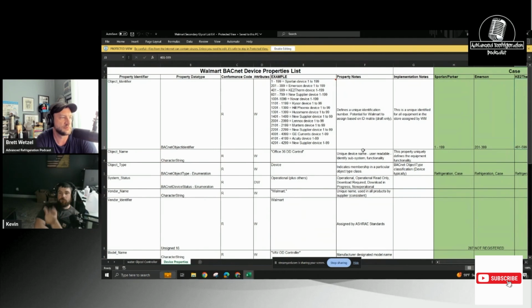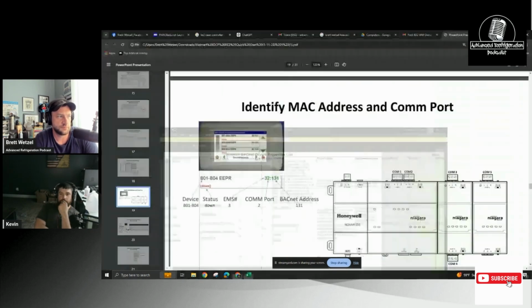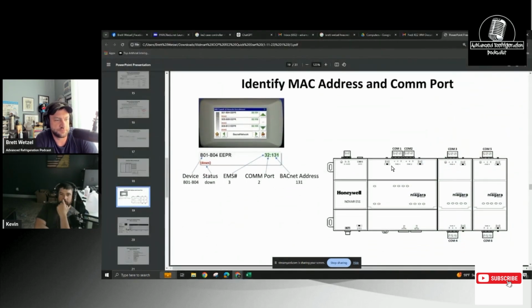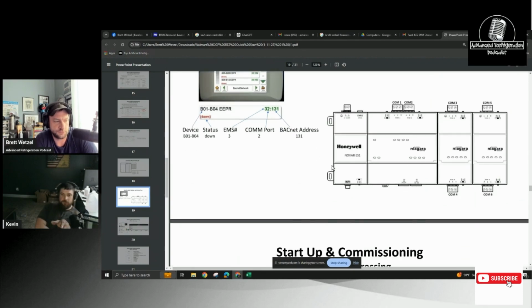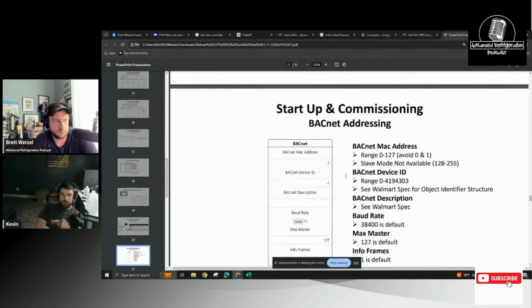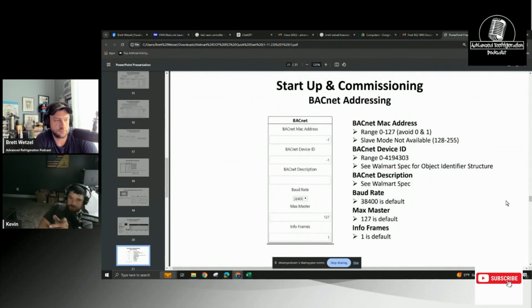Go back to that screen where you had the Novar stuff up. I want to bring this up because it came up with the CC200s. Go down, I think it's okay right there. See where it says Max Masters, default is 127. If that isn't set high enough for the number of case controllers you have, you can only bring on so many. I had an E3 where the Max Masters was set to 10.